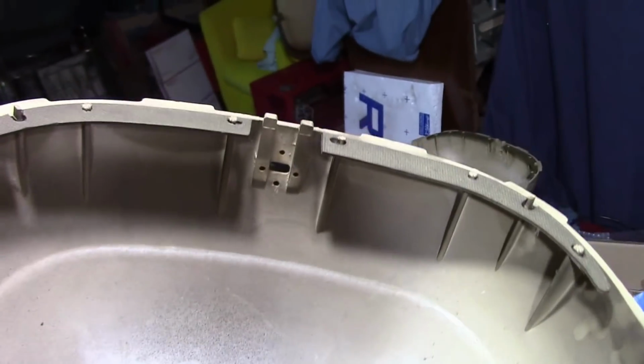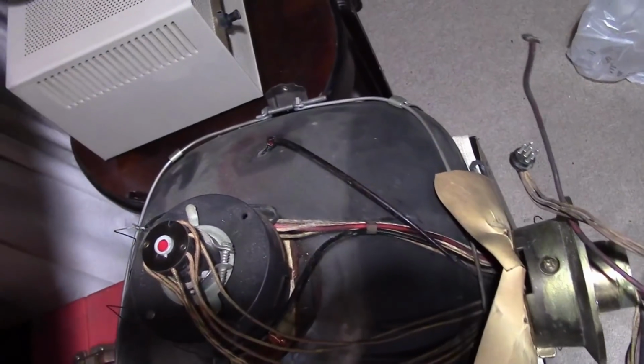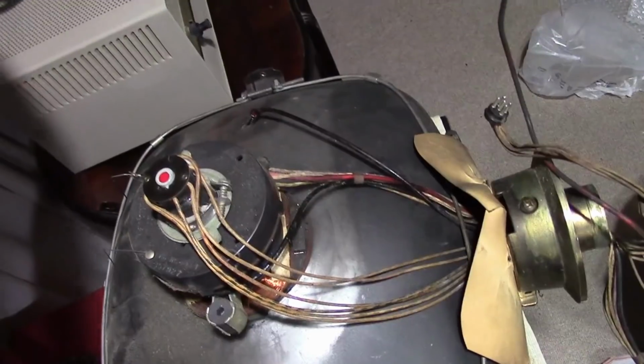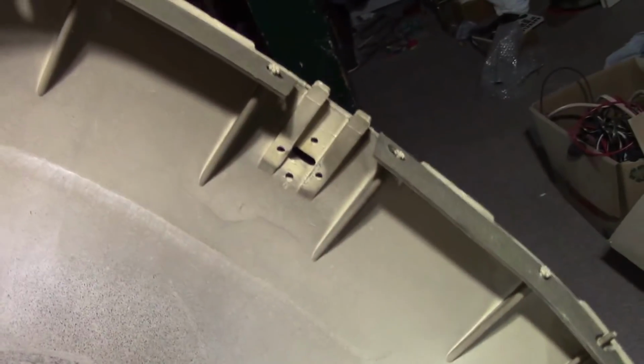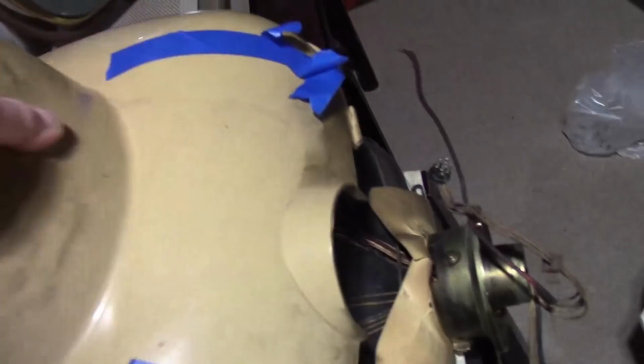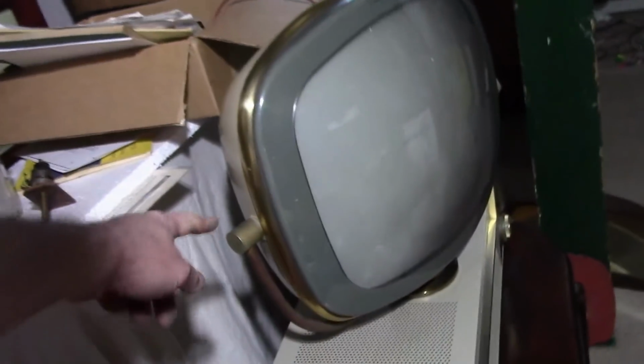So what's different about that side of the back? That's where the high voltage lead connects. If it slipped off and hit that retaining system around the rim, that's grounded, so it'd short out the high voltage. What I'm thinking this is there for is in case that high voltage somehow made it past the grounding strap and touched the metal cap on the outside of the metal bar. I think that's there to prevent any possibility of that high voltage making contact with that, which of course could shock somebody.